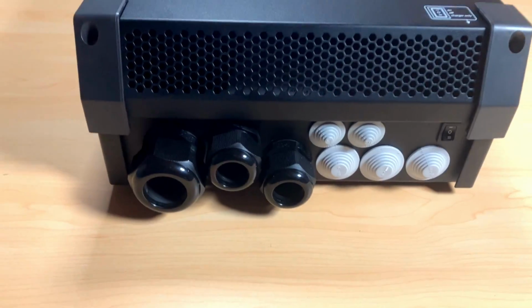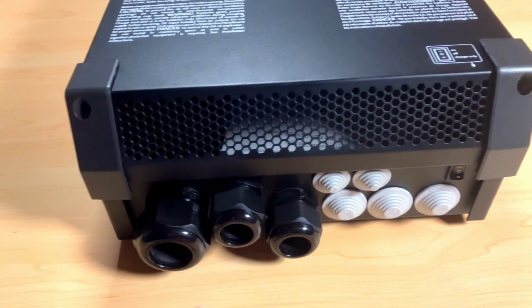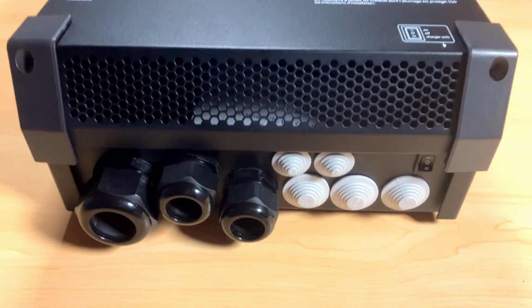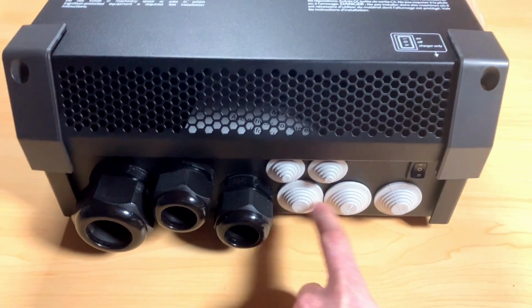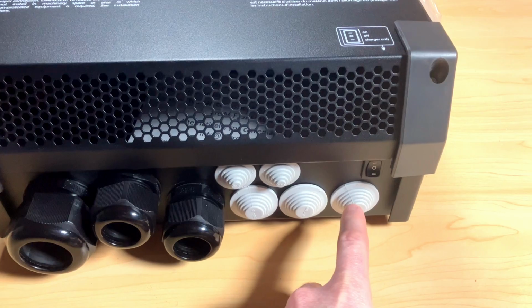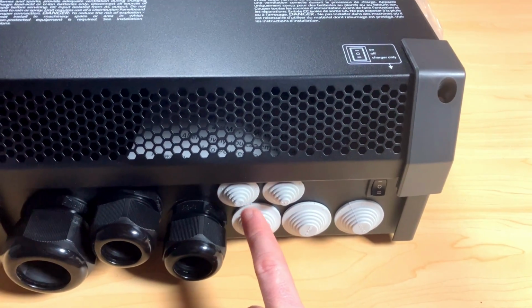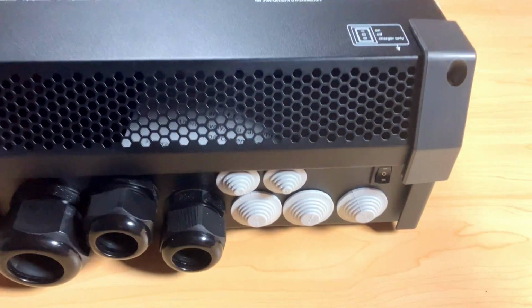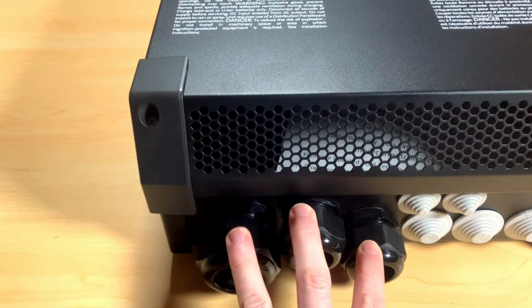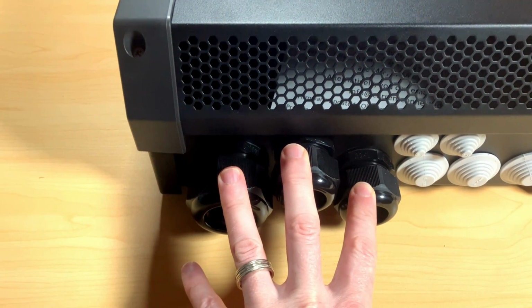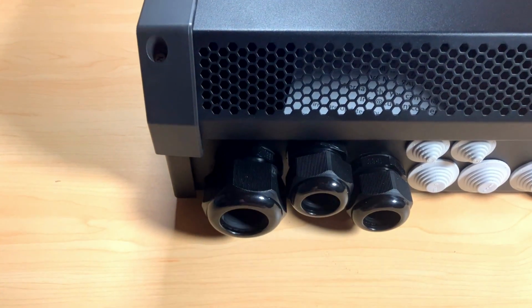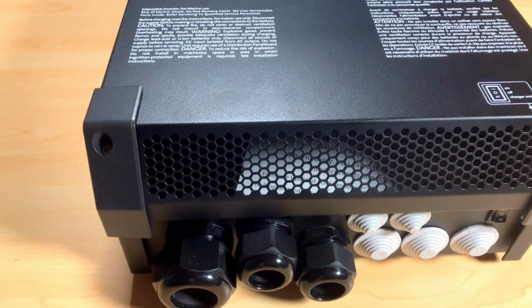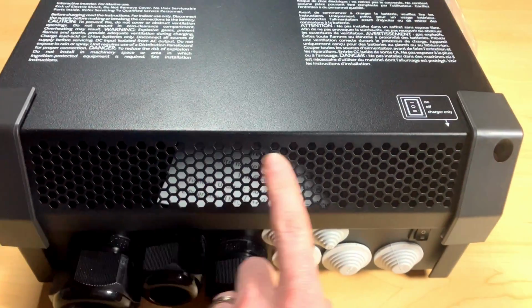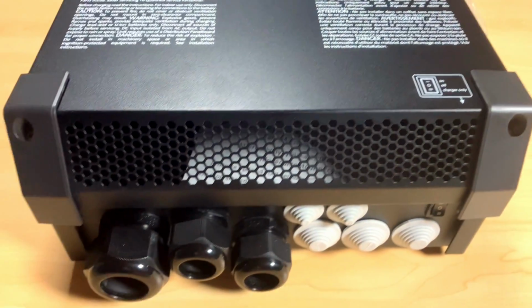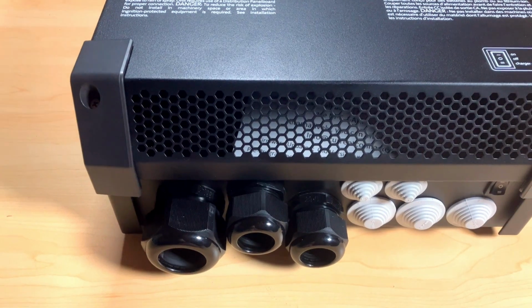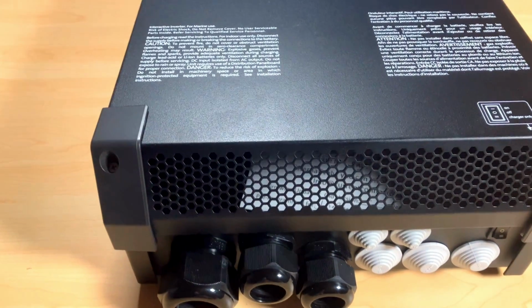Looking at the bottom here, we've got 3 different style cable glands, because normally I remember seeing in all the old units they have all these multi-sized fittings to where you basically cut the size that you need for your cable to slide through. But they've got these larger sizes on here now for the AC side. I believe this all has to do with, including the way this hexagon pattern is down here, the UL 1741 compliance.